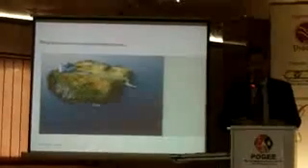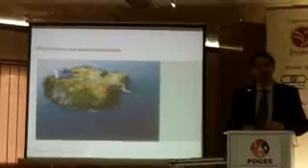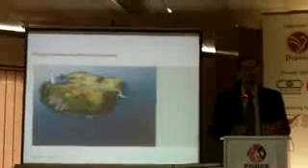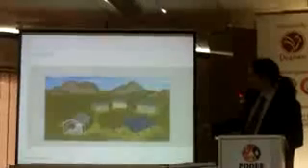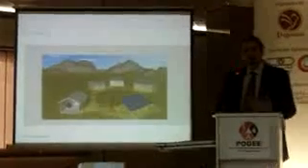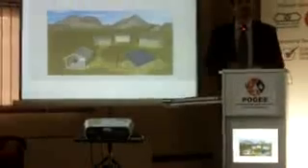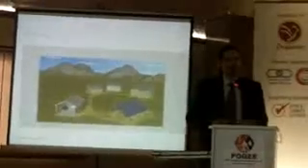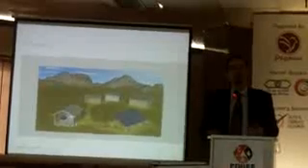Now, away from the big things, coming to the villages, the small electrifications. So this is an island. Island or village electrification could also be a remote place in Balochistan, where where never the grid reaches, you can set up an inverter that is able to work bidirectionally with a battery and form a normal AC grid. It's a kind of micro utility. It is forming your 230 volt, 50 Hertz grid, and now you can connect your loads, but you need, of course, a generating source, and this is PV.